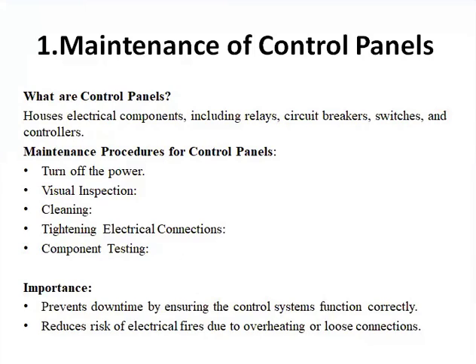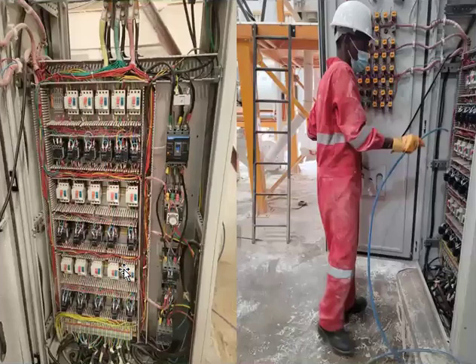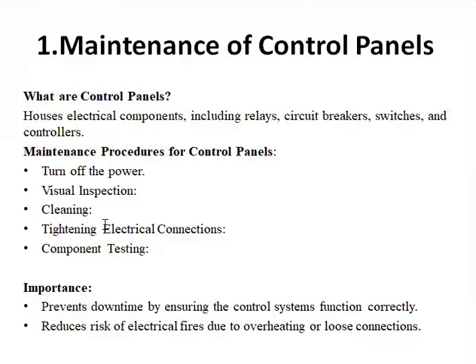Then we have component testing. We test each component in case of any failure. So you may find the circuit breaker here is not working. If this circuit breaker or this contactor is not working, the system will have a problem. So we need to test each component against its functionality. It is of great importance because it prevents downtime by ensuring that the control system functions correctly, and reduces risks of electrical fires due to overheating and loose connections. Overheating from a loose connection can affect a component and lead to overheating of the motor as well.